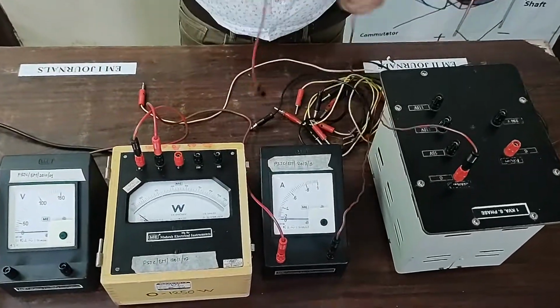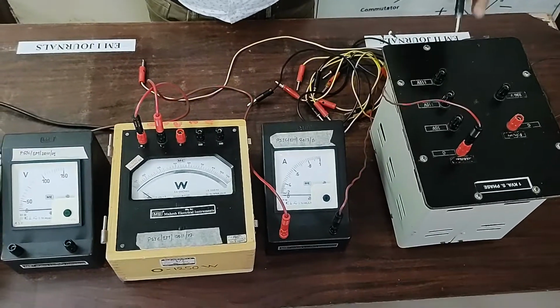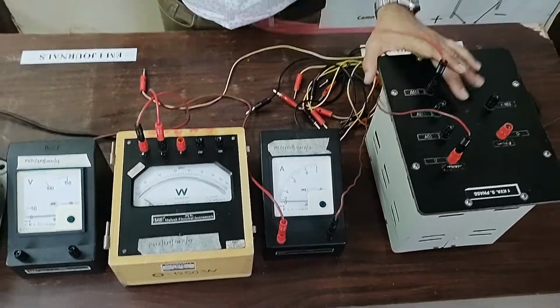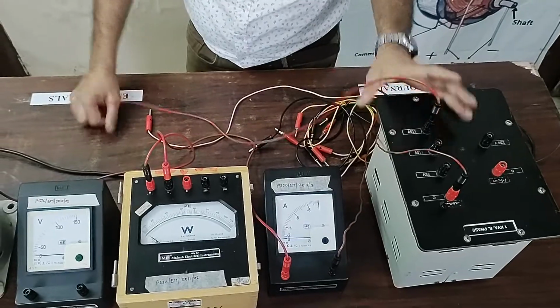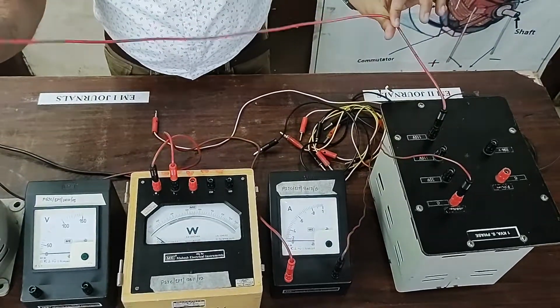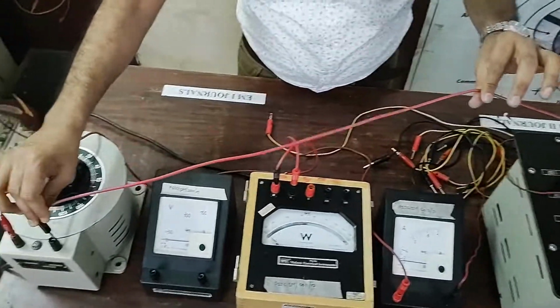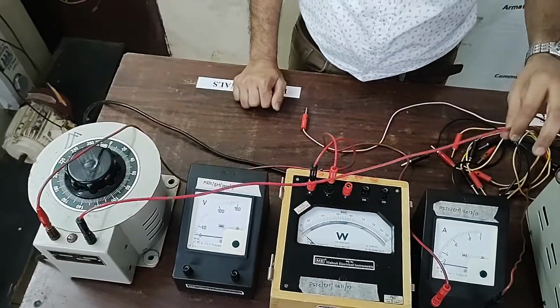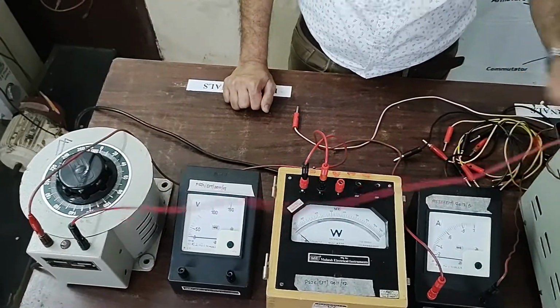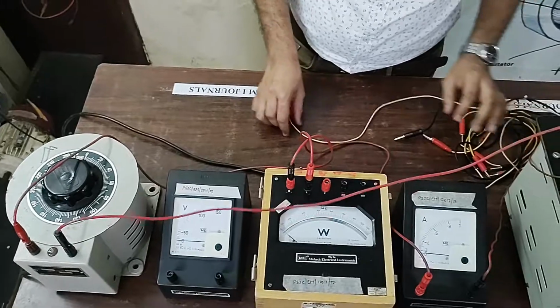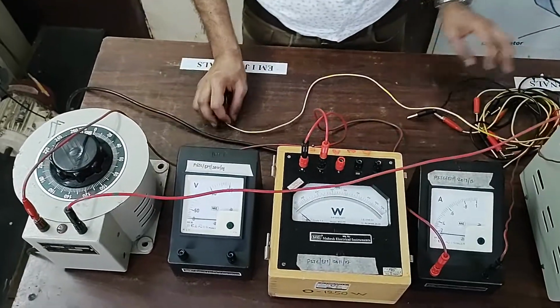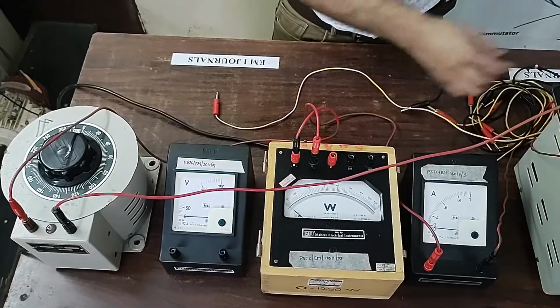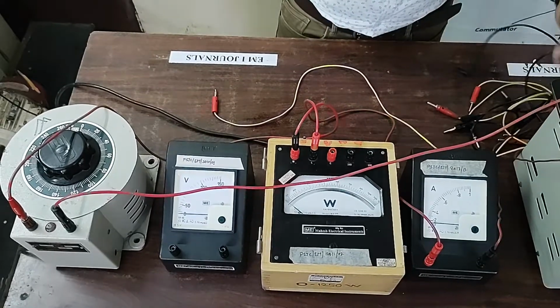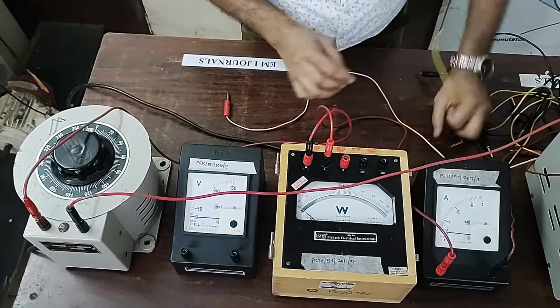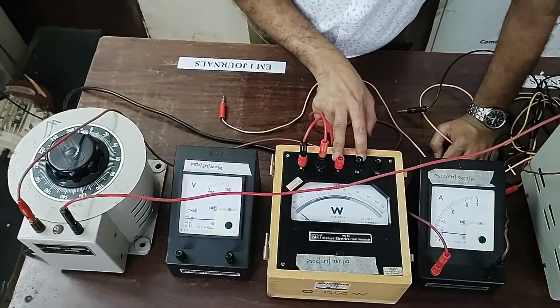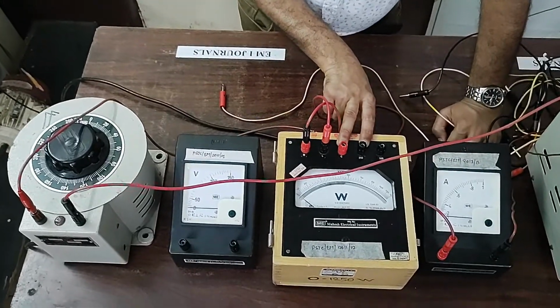So now from the neutral point of the primary winding of the transformer, we have to take this connection directly across the neutral of the auto transformer. So this forms one part of the circuit. Next we have to take a small connecting wire, because we know that we have to bring the voltage coil in the circuit as well.